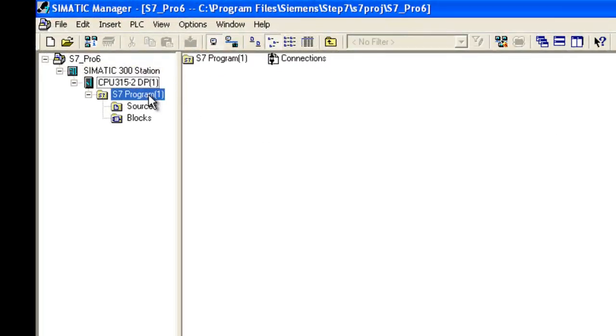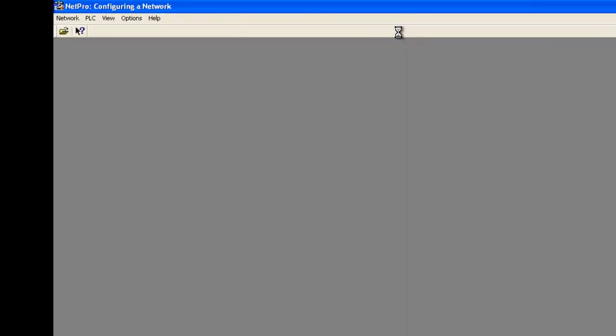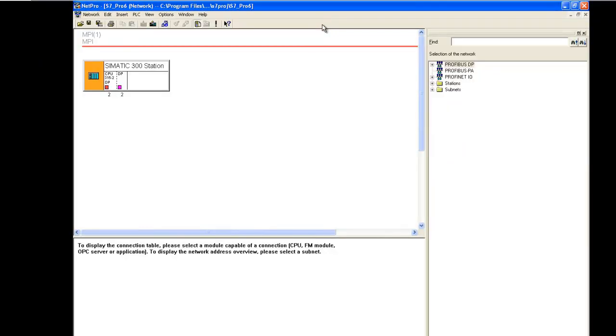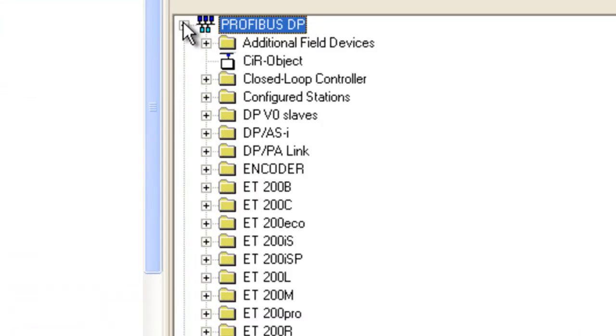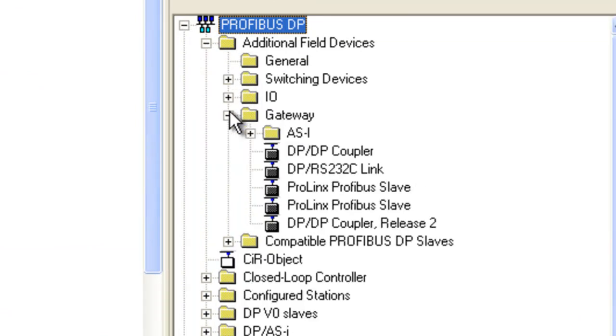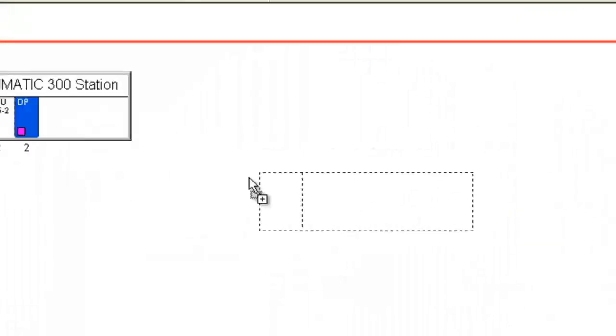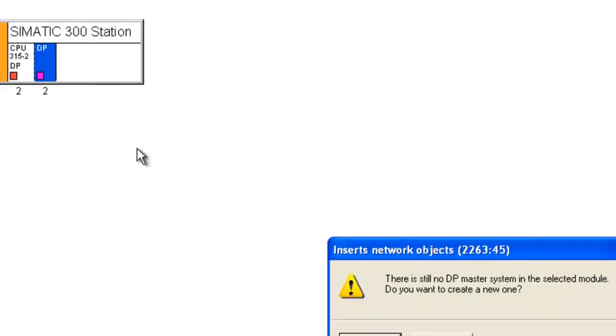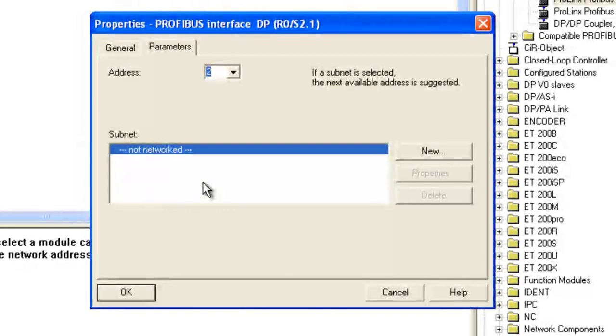And this is where we're going to go into the configure of the network. So we'll first have to click on the DP module and go over to the catalog where our GSD file is at, which is going to be under Gateway. And it's going to be the ProLinx Profibus Slave. So we'll go over and drag out to the Profibus Master. It's going to ask us if we haven't configured a master we need to, so we'll go ahead and configure the master.